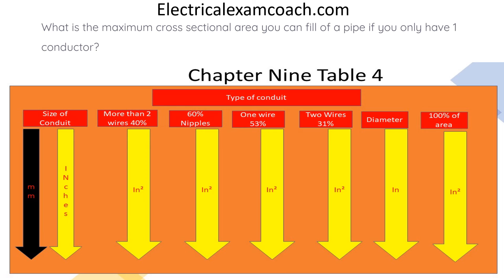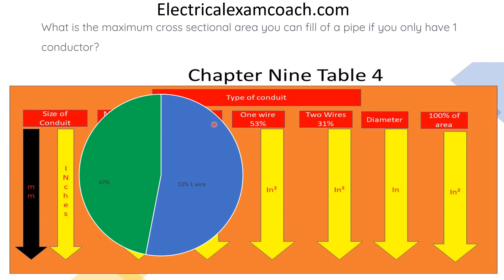We find this in Chapter 9, Table 4. We always check the type of pipe, but in this case it doesn't matter because the fill percentages are the same across all these tables. On the left-hand side is our conduit size. If you have more than two wires, the fill is 40%; nipples or other 60% conditions apply at 60%; and if you're only doing one wire — such as a grounding electrode conductor — you're only allowed to fill that pipe 53%. Visually, imagine looking directly at the end of a pipe: you're allowed to fill 53% of that cross-sectional area.